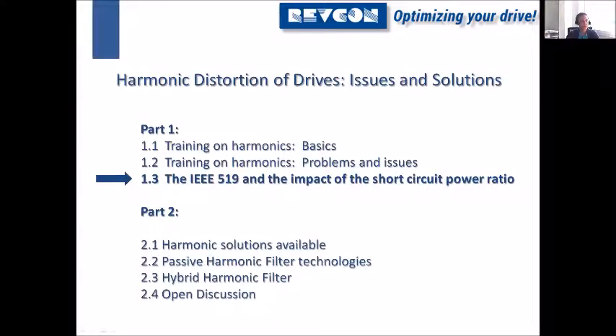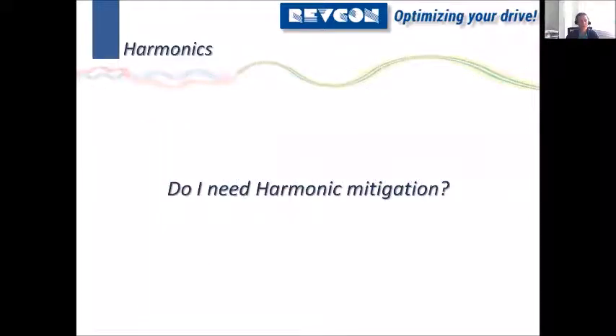Okay, so the next part is a little bit more intense: the IEEE and the impact of the short circuit current ratio. The question you always ask yourself when we speak about harmonics is, do I need harmonic mitigation? When you do a big drive, do I need harmonic mitigation? This morning I held a seminar for Asia, and they always put harmonic mitigation on today, at least for HVAC projects. But I think in most other parts of the world, harmonic mitigation is a decision to be made, and it depends on some quite relevant factors.